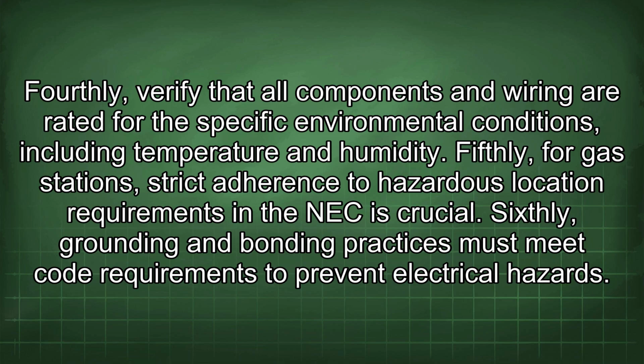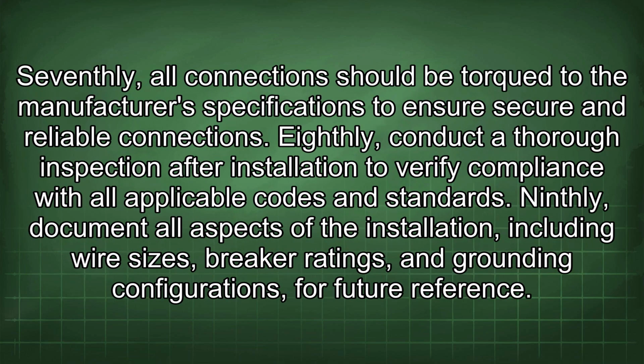Sixthly, grounding and bonding practices must meet code requirements to prevent electrical hazards. Seventhly, all connections should be torqued to the manufacturer's specifications to ensure secure and reliable connections. Eighthly, conduct a thorough inspection after installation to verify compliance with all applicable codes and standards. Ninthly, document all aspects of the installation, including wire sizes, breaker ratings, and grounding configurations for future reference.